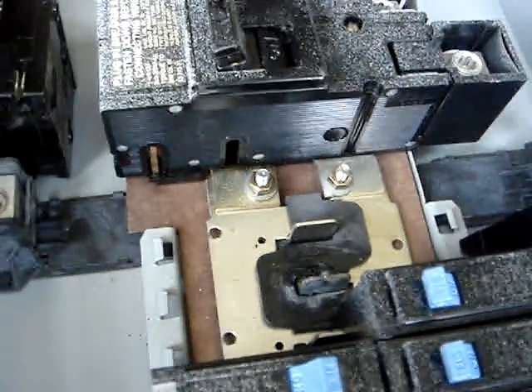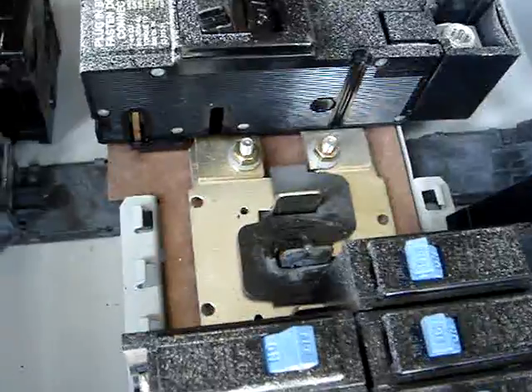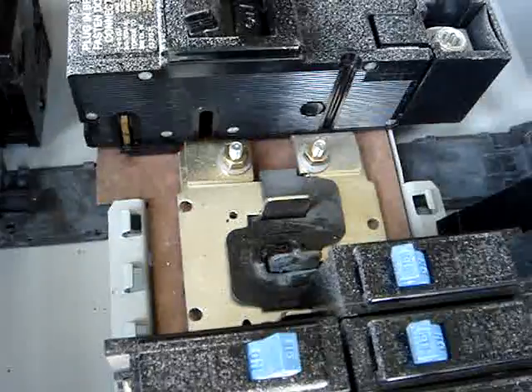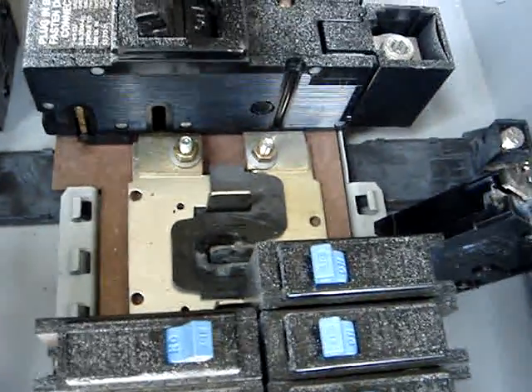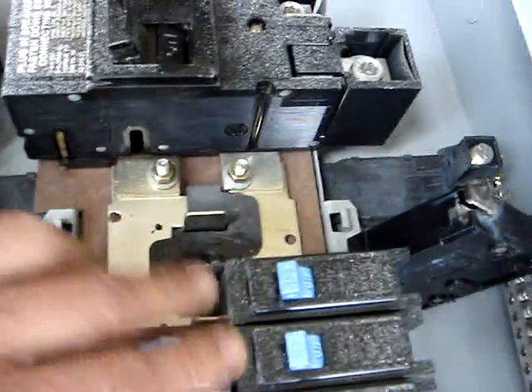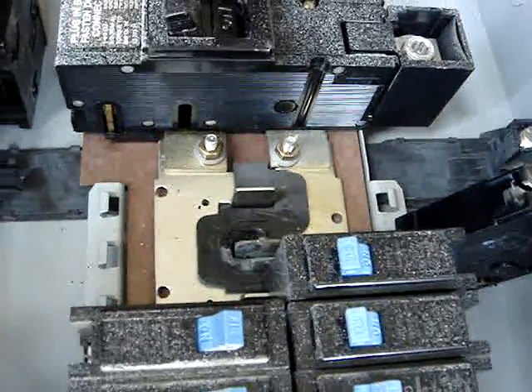What happened was that I was trying to isolate a wiring circuit for a lamp. I had to throw off the breakers. When I turned them back on, there was a popping or crackling sound that came from the breakers up on this tab on the bus bar. At the time I didn't know what was causing it, but I called Home Depot. They said to just push down on the breakers to make better contact. I did that, and the noise stopped. I thought problem solved — and I was wrong.